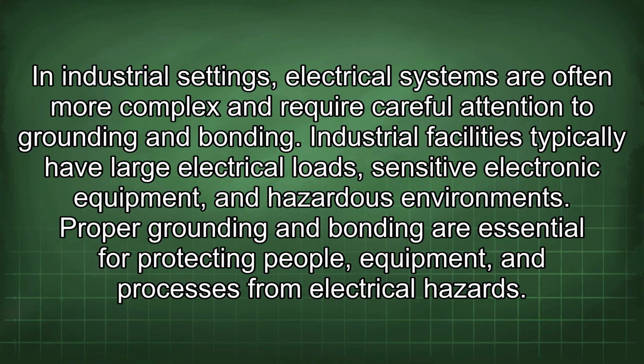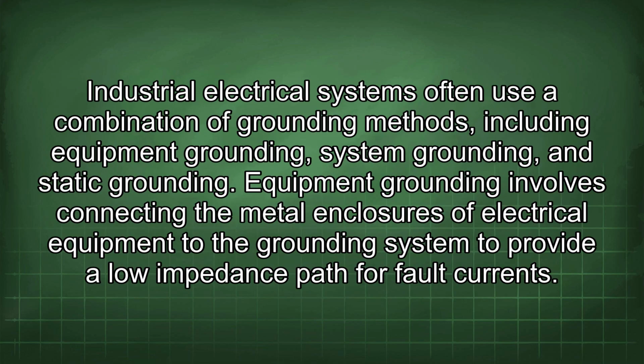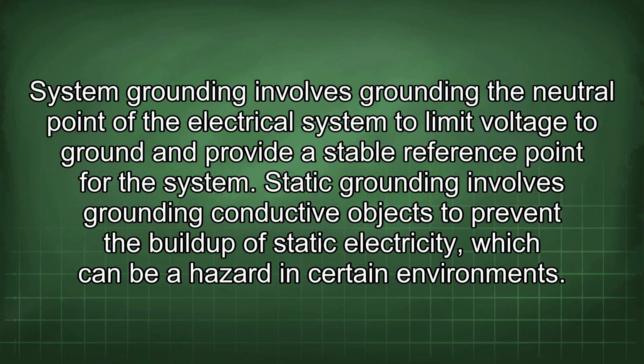Industrial facilities typically have large electrical loads, sensitive electronic equipment, and hazardous environments. Proper grounding and bonding are essential for protecting people, equipment, and processes from electrical hazards. Industrial electrical systems often use a combination of grounding methods, including equipment grounding, system grounding, and static grounding. Equipment grounding involves connecting the metal enclosures of electrical equipment to the grounding system to provide a low impedance path for fault currents. System grounding involves grounding the neutral point of the electrical system to limit voltage to ground and provide a stable reference point for the system.